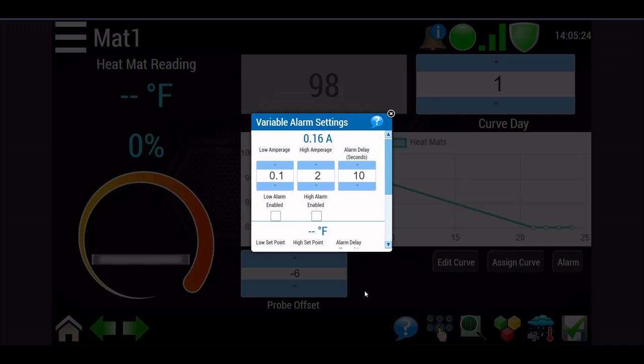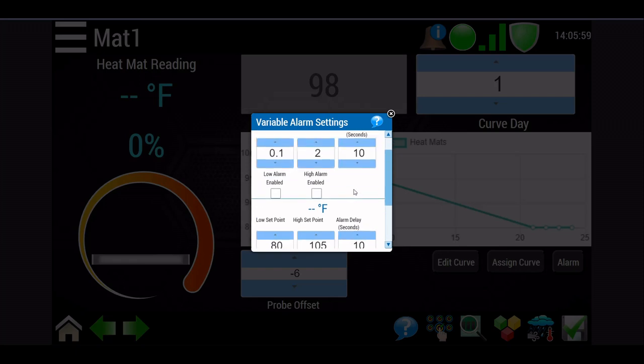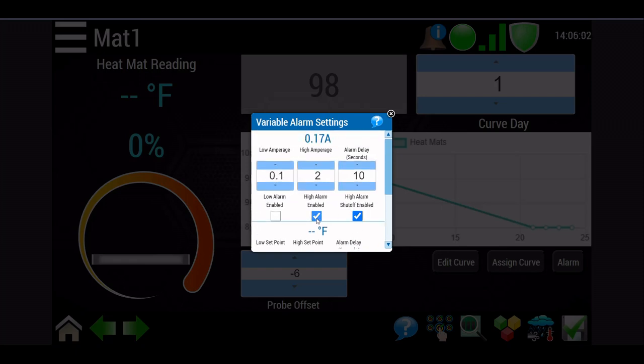So in the alarms here, we have our low and high amperage that can be enabled if you want them, and our alarm delay in seconds. And that alarm delay is just the amount of time that the alarm condition needs to be present for that alarm to actually go off. So if we're at 2.1 amps for 5 seconds, we're not going to get an alarm. We need to be at over 2 amps for at least 10 seconds for us to trigger that alarm. And obviously right now our alarms are disabled, so it wouldn't alarm.